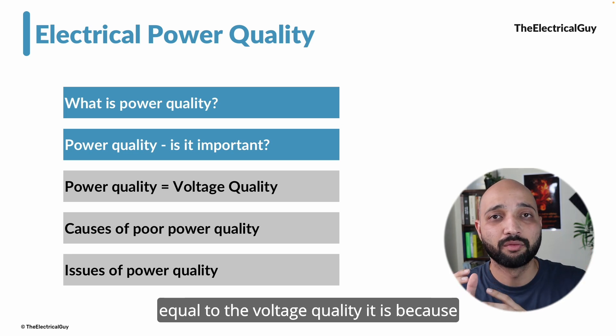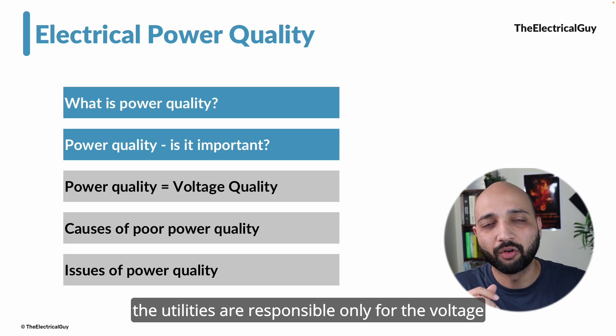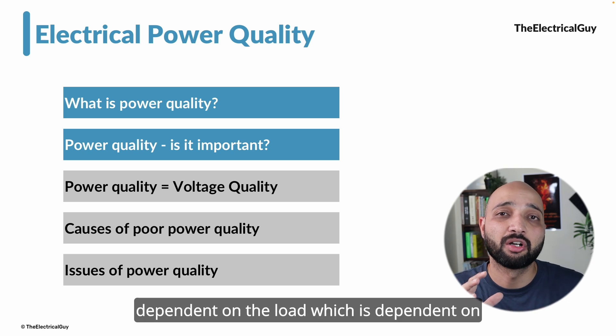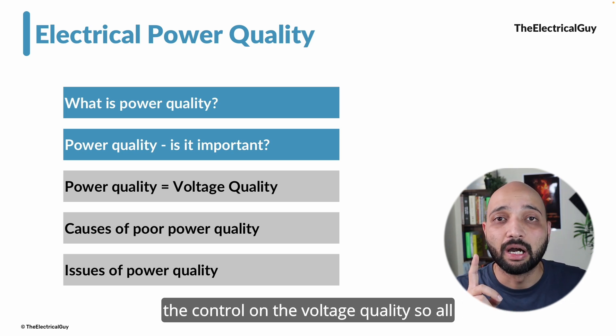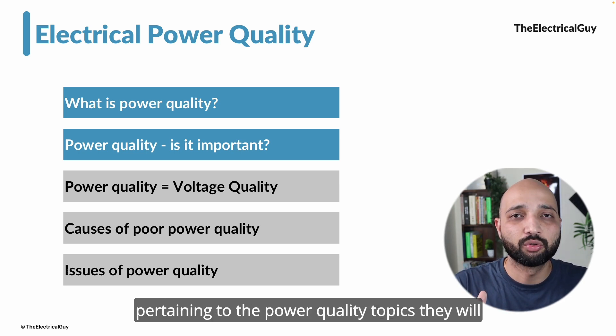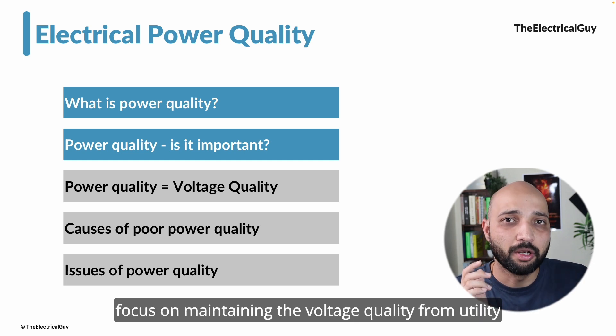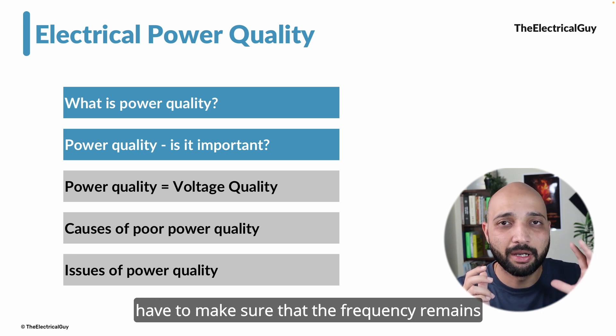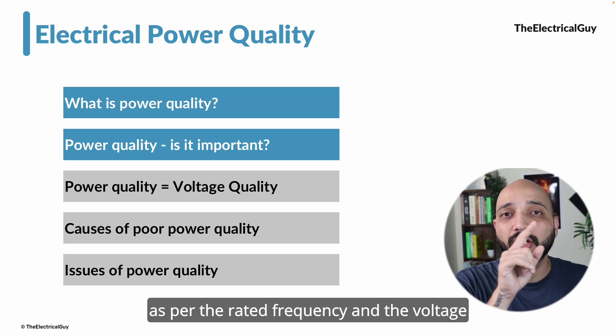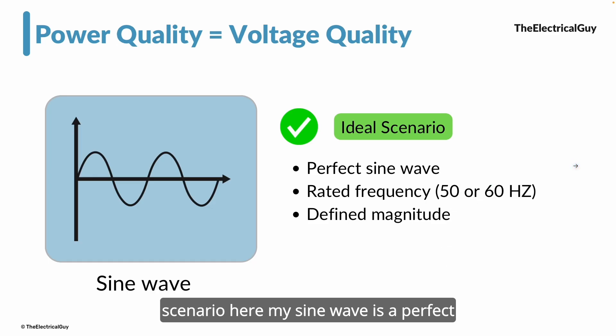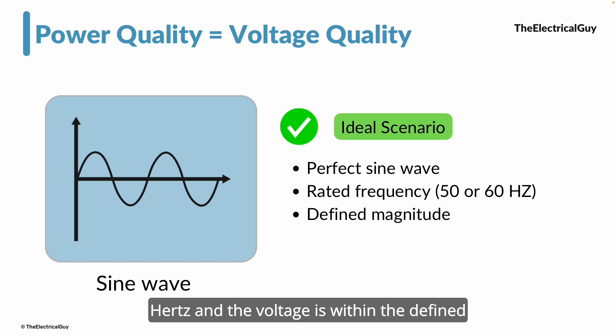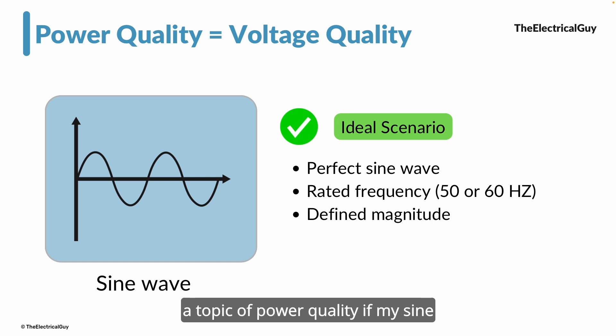Power quality equals voltage quality because utilities are only responsible for the voltage. How much current is drawn depends on the load, which depends on the customer — so utilities don't have direct control over current, but they do control voltage quality. All power quality standards focus on maintaining voltage quality from the utility side. Utilities must ensure frequency remains at rated value and voltage remains a sinusoidal wave. In the ideal scenario, the sine wave is perfect, at the rated frequency of 50 or 60 Hz, and the voltage is within the defined magnitude.